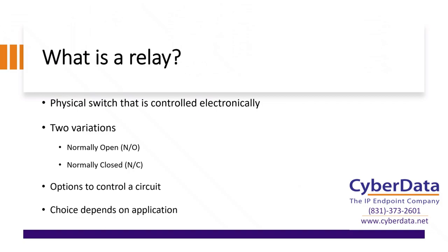There are two different variations you can run into when dealing with relays: normally open, commonly referred to as NO, or normally closed, NC. These are basically two different styles of a circuit where some devices need to be consistently energized with a normally closed circuit and then you de-energize the system for it to take an action. Or the inverse, where the circuit is normally not completed — the circuit is open — and you toggle the relay to temporarily close the circuit so that electricity can flow. You need to know the style of circuit you're working with — normally open or normally closed — to pick the right unit.